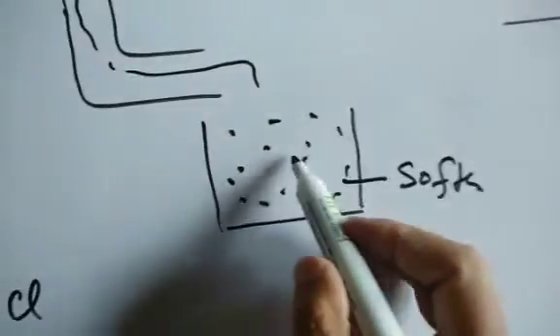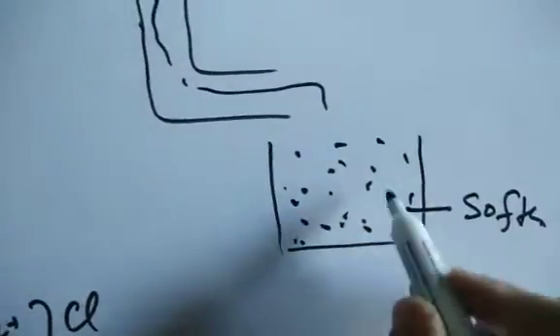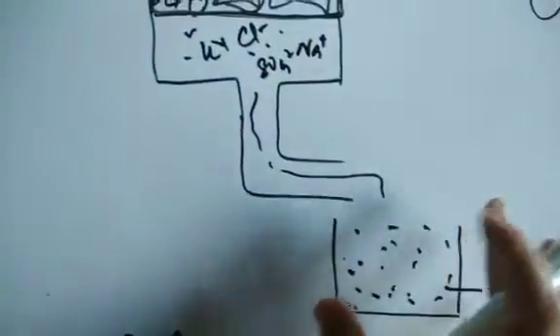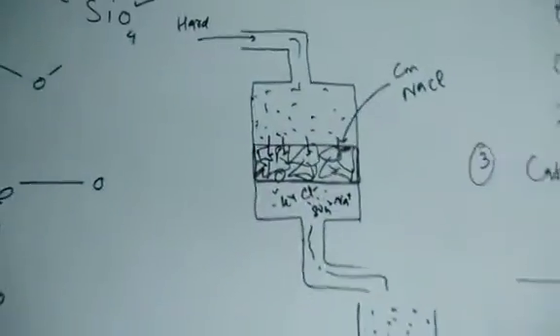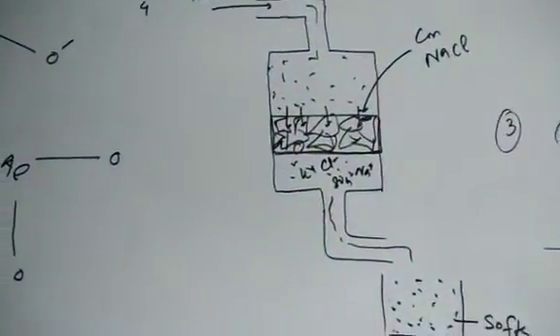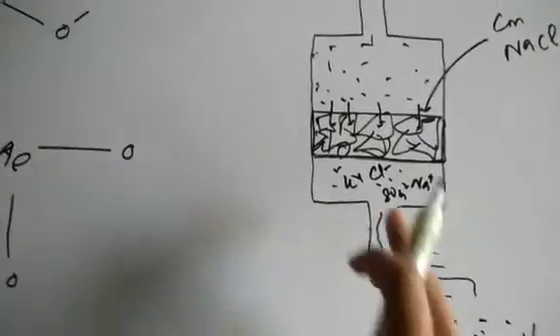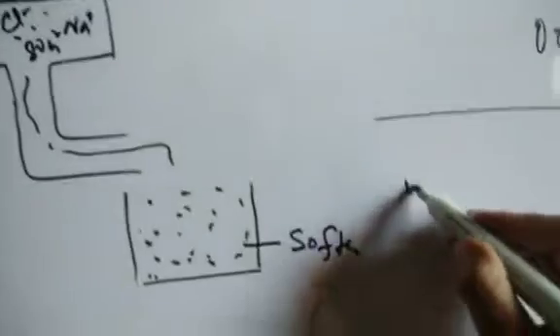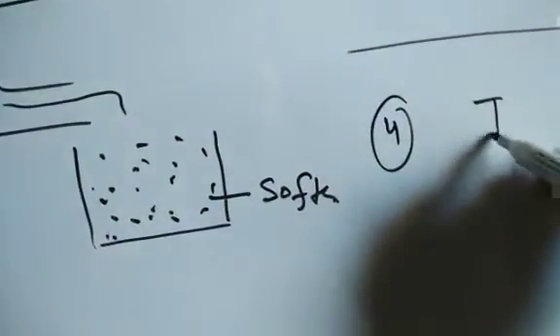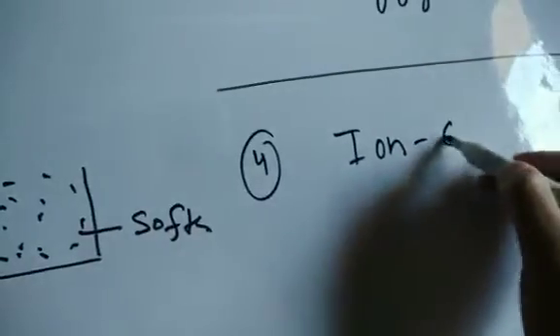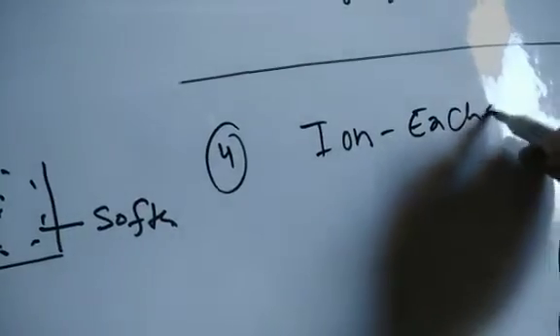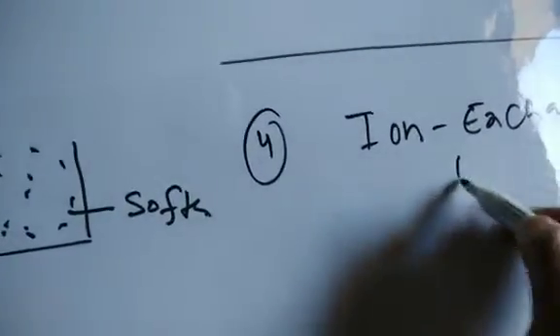Note that this process cannot be called de-mineralization or de-ionization, because anions like chloride, sulfate, and bicarbonate are still present in the treated water. This process is specifically called softening of water, as only hardness-causing cations are removed.